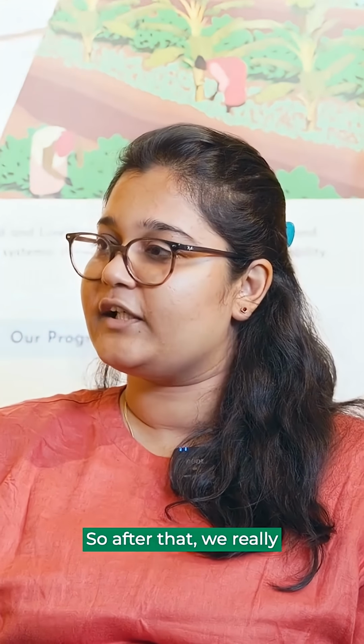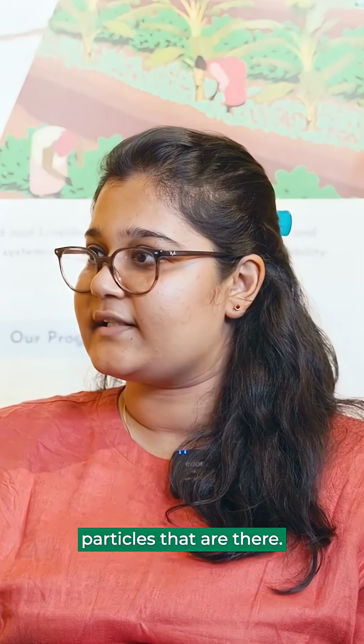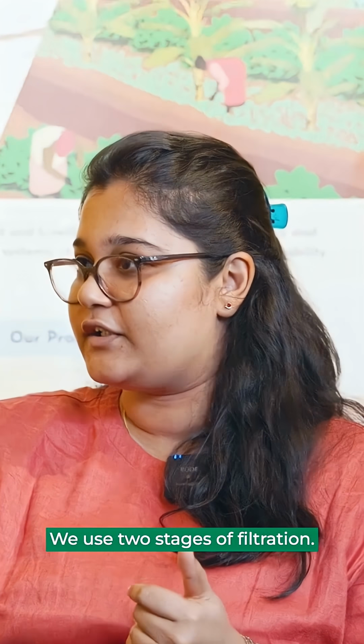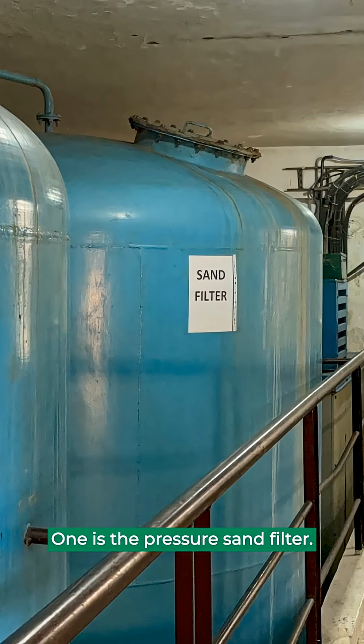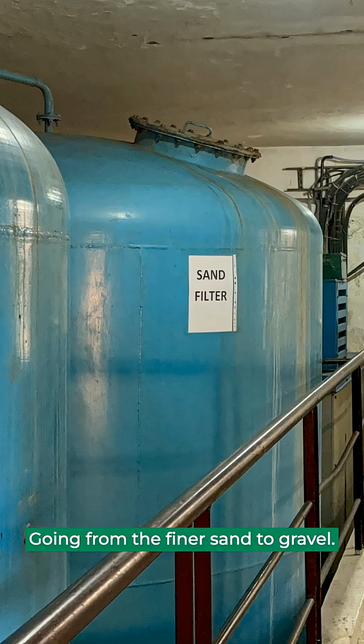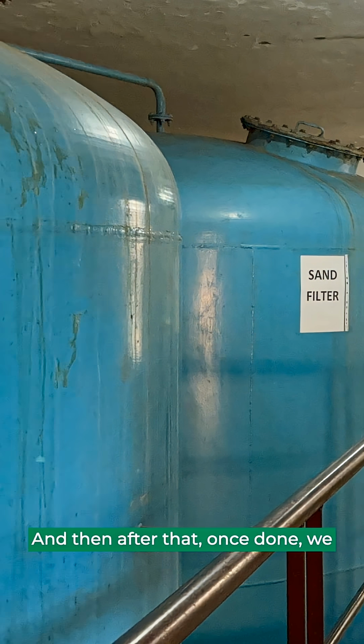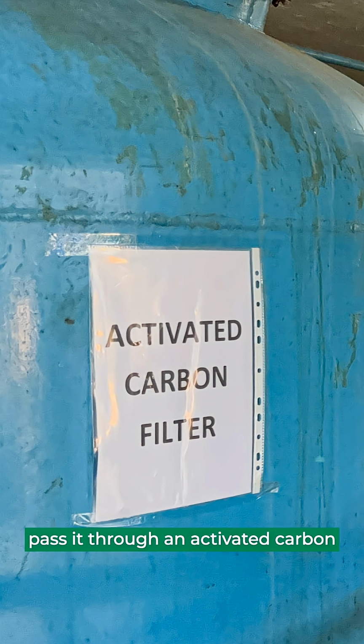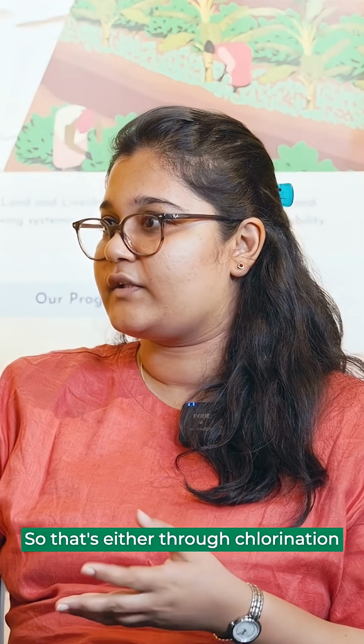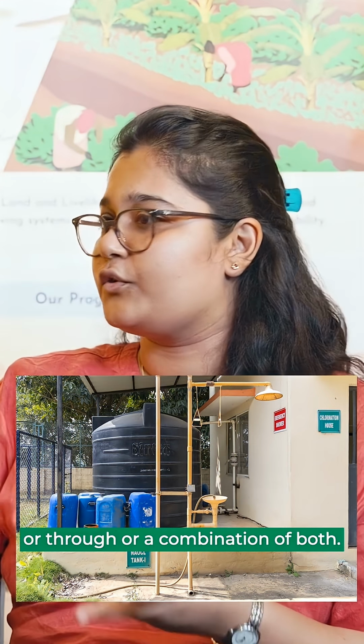So after that, we really want to remove the finer particles that are there. We use two stages of filtration. One is the pressure sand filter. Essentially, it goes through different layers of sand, going from the finer sand to gravel. And then after that, once it's done, we pass it through an activated carbon filter to remove anything else. And then after that, we disinfect. So that's either through chlorination or through a combination of both.